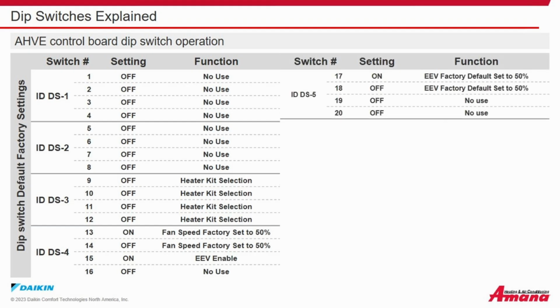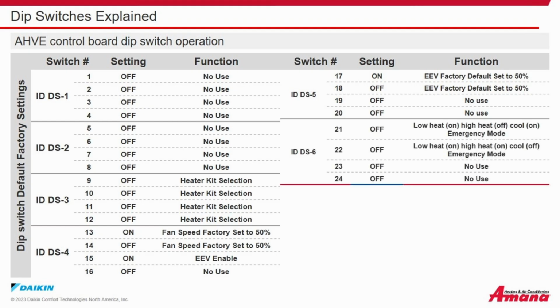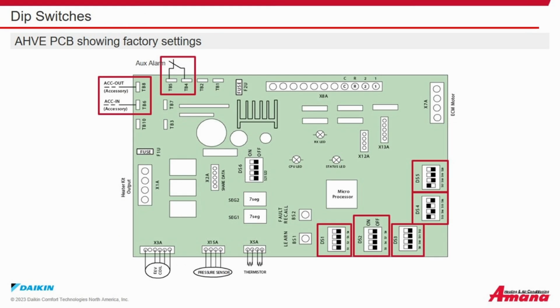DS5, 17 on and 18 off, set the factory default EEV setting to 50%. 19 and 20 are not used. DS6, 21, low heat on, high heat off, cool on in emergency mode. Switch 22, low heat on, high heat on, cool off in emergency mode. Switches 23 and 24 are not used. This diagram is showing the factory settings on the AHVE printed circuit board.